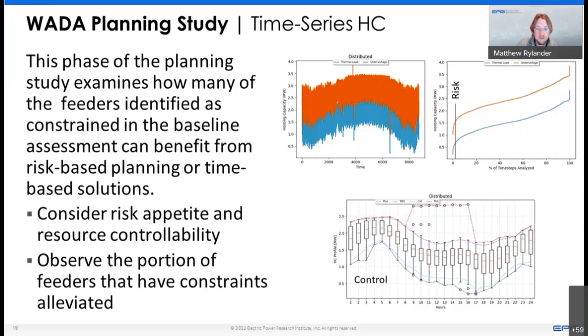So that's where time-based hosting capacity came into play for us. We can look across the grid and see the capability to utilize it at certain points in time. Going back to the slide Fiona showed, worst-case planning analysis might identify—here I've pulled out the top 10 to 20 feeders with the worst-case impacts—feeders with very significant limitations and not much hosting capacity at all. But by utilizing either the risk aspect or, more specifically, the control aspect, you can see a lot more ability to accommodate these new resources.